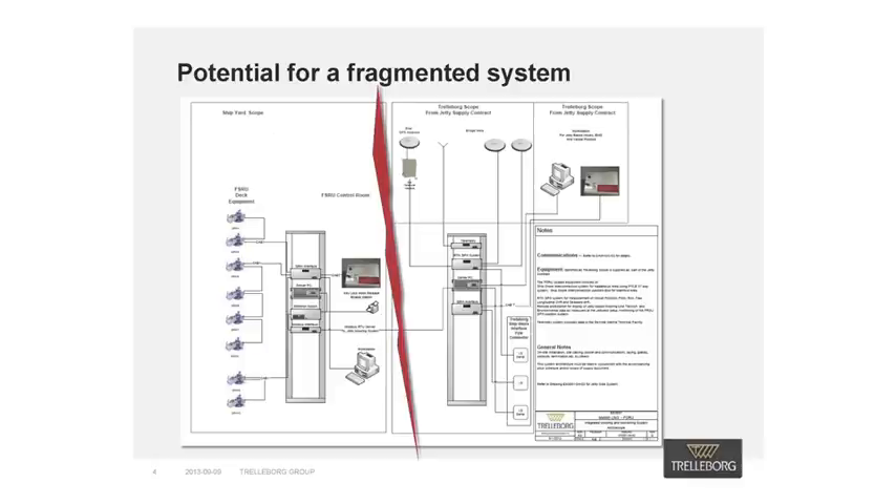The location of radio and GPS transmitters needs to comply with hazardous zoning as well as avoidance of reception shadows. Critical berthing aids, such as the display board, must be sited so the line of sight of the LNG carrier's deck officers is unimpaired throughout all phases of docking and undocking. Unimpaired service access needs to be carefully considered in order to assure ease of routine maintenance and repair of all equipment.